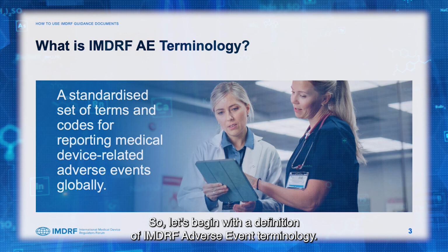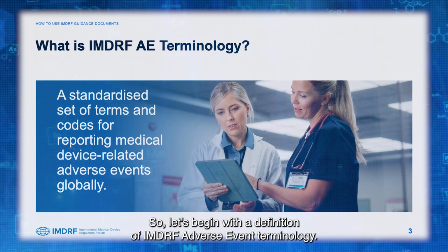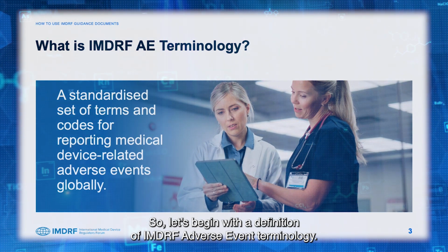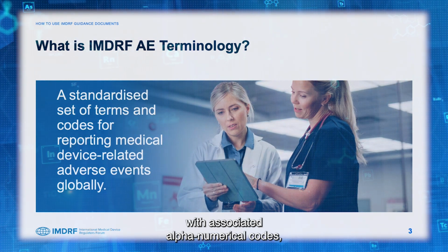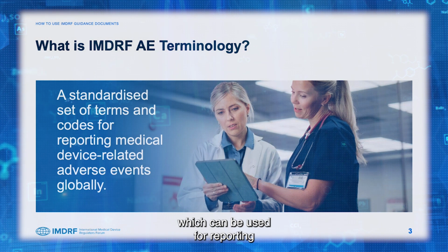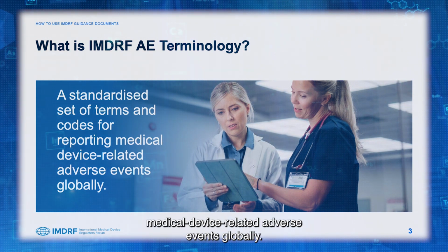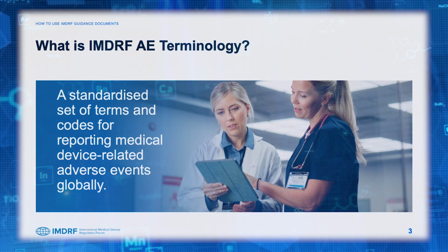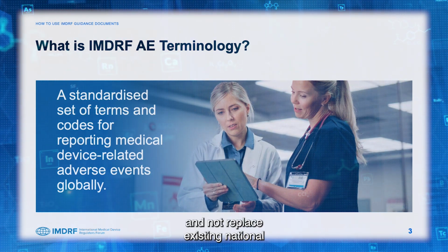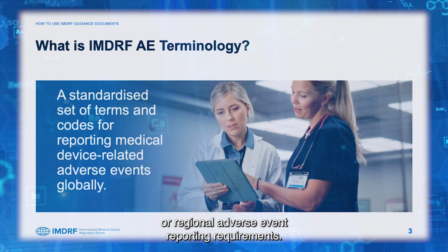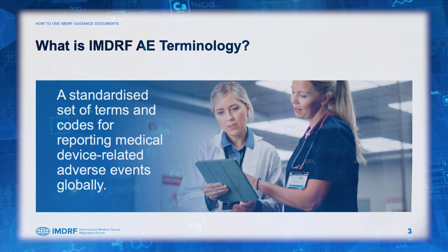So let's begin with a definition of IMDRF adverse event terminology. It is a standardized set of terms with associated alphanumeric codes which can be used for reporting medical device-related adverse events globally. It is designed to enhance and not replace existing national or regional adverse event reporting requirements.